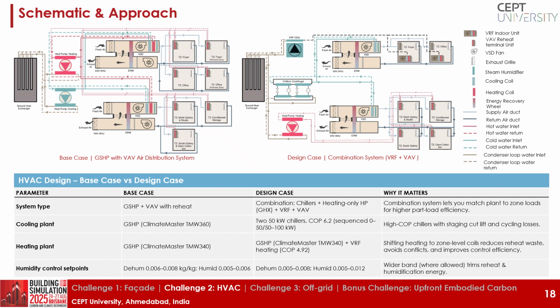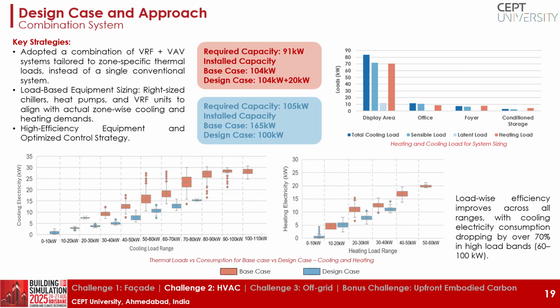Altogether, the combination system offered much better flexibility, efficiency, and zone-specific performance compared to the original base case. The thermal load versus consumption plots for the base case and design case show that in the cooling profile, the base case shows consistently high electricity use across all load bands. In contrast, the design case follows the load much more closely with a sharp improvement at higher loads. In fact, between 60 and 100 kilowatts, cooling electricity consumption drops by more than 70%.